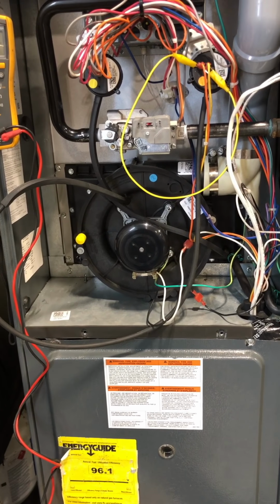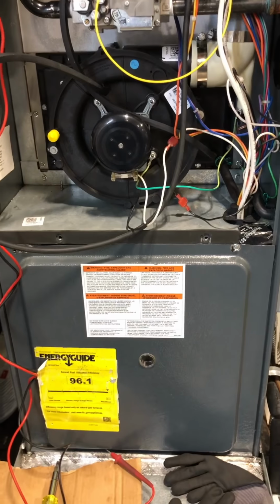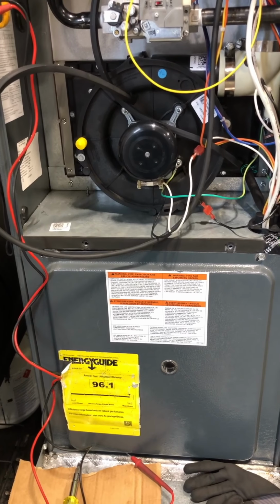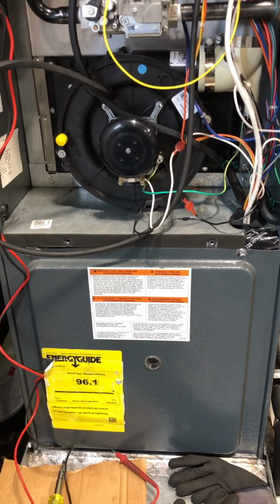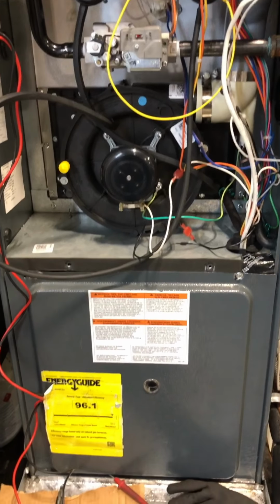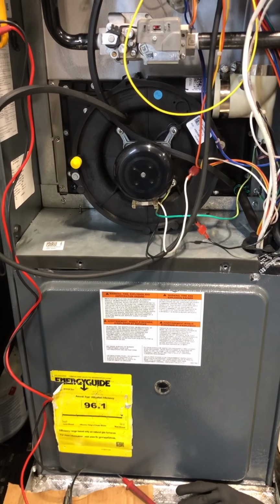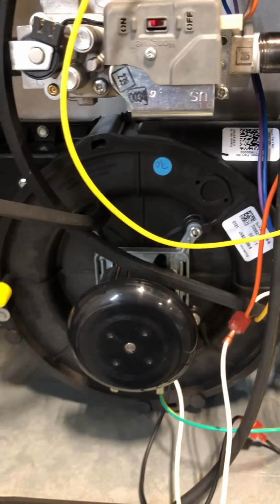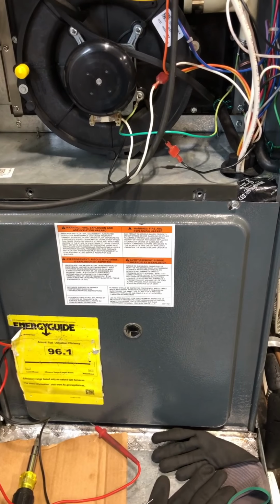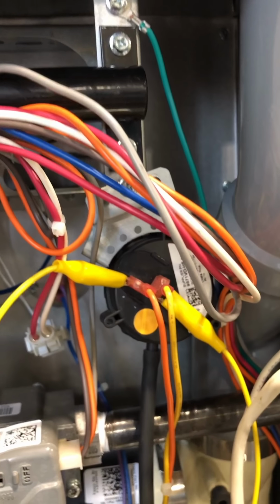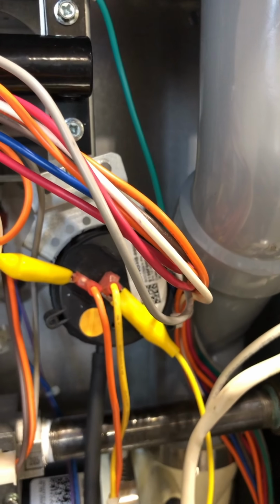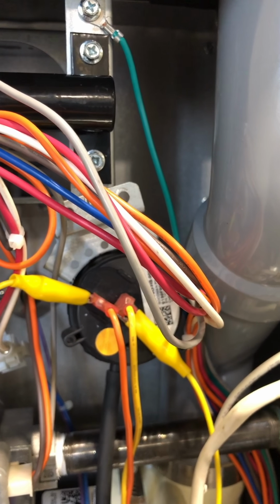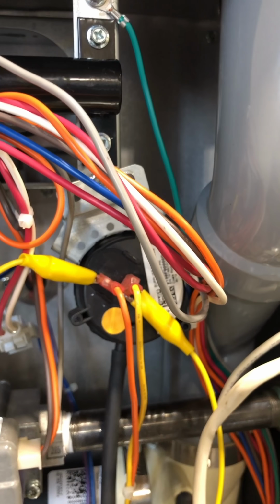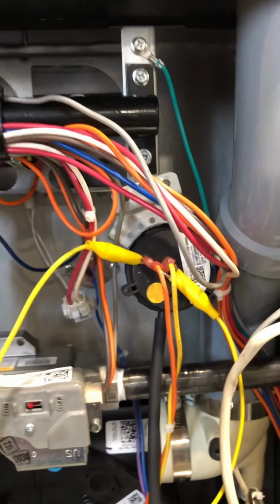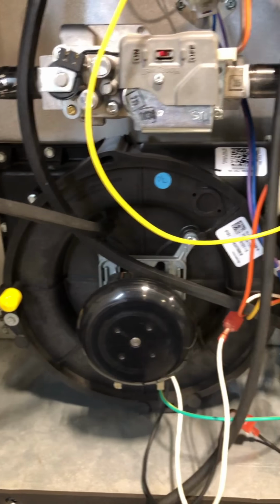Now in most furnaces, whenever there's a malfunctioning safety switch, the board automatically brings the blower motor on just in case we have an overheating type of situation. It brings the blower on for safety to try to cool the heat exchanger down. It doesn't know what's really going on, it just knows that one of the safeties is open. So it automatically brings on the blower motor. There's my call for heat, but no inducer motor. Because the board has noticed that this switch is closed, is passing 24 volts through that switch. It's not going to go any farther. It needs to verify that that switch is open and not stuck before it will start the inducer and continue the process. Call for heat. No inducer motor, but the blower motor came on.